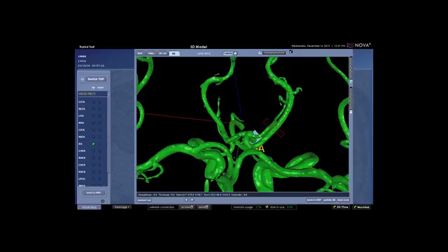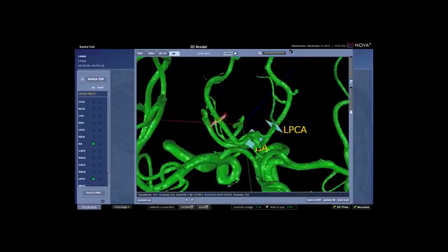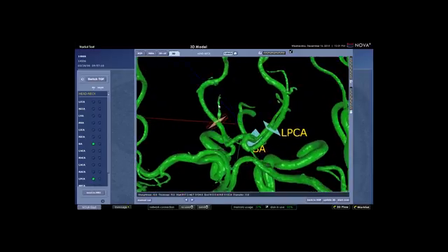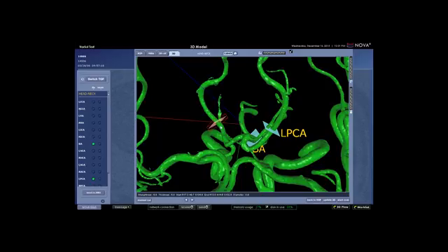Here's the left PCA. Just click with my mouse and select the appropriate label from the drop-down menu, and right PCA. And notice Nova has automatically oriented that perpendicular, and the algorithms determine the center scan line, so I can actually walk this cut up and down the vessel segment and maintain that perpendicularity. So red axis is the patient's right, just a right click now to label that.